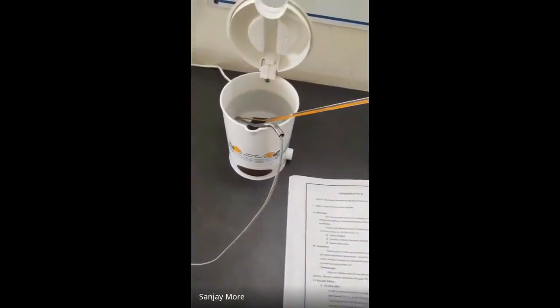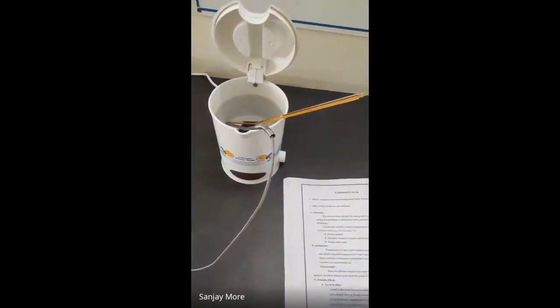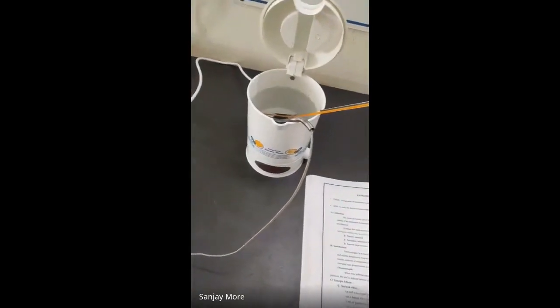So this is our experiment number one, temperature measurement using thermocouple and thermometer. Aim of this experiment is calibration of thermocouple, means you have to check whether the reading given by the thermocouple is correct or not. Okay. And all of you draw this observation table. This is mercury thermometer reading in degree Celsius. First, room temperature is considered as 30 degrees Celsius. Also thermocouple calculated room temperature as 30 degrees Celsius. Then potentiometer reading is 0.2 MV. Then after some heating, the water temperature is considered as 64 degrees Celsius. Then 40 degrees Celsius is the thermocouple reading. Then the difference is 24 degrees Celsius.